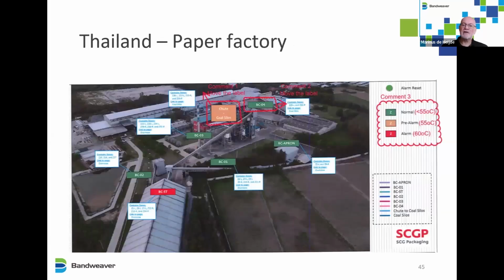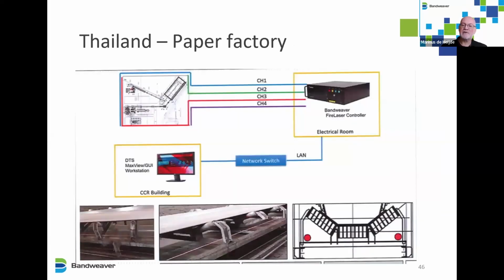And last of all, in Thailand, we did a very big paper factory where alarm settings were used for 60 degrees, pre-alarm at 55. And as you can see, there was quite a few different belts and zones involved there. So we used a 4-channel unit. The unit was installed in the electrical room, and then via network switch, we connected it to a MaxView workstation. And as you can see, this is again a slightly different bearing setup.